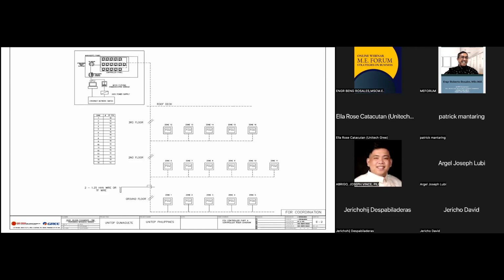RS485 module, a communication module. The RS485 is a connection wire that goes through a multiplexer system. When I say multiplexer system, basically from a single frequency unit it will divide into many frequencies. In this scenario, the main source of information comes from our communication module, our CPU. Through the process of multiplexing, I segregated the information for each FCU, divided into different zones.